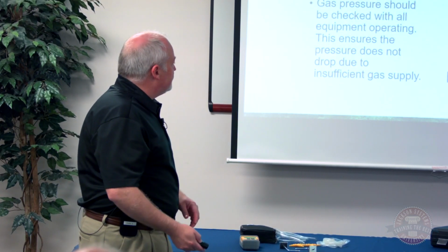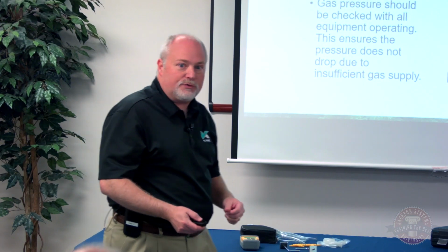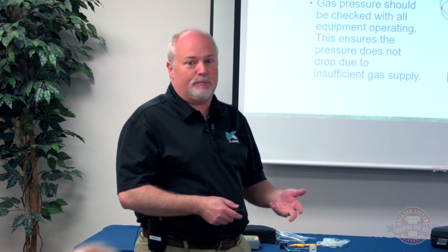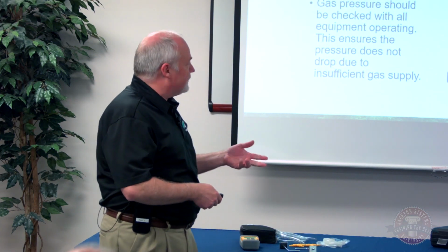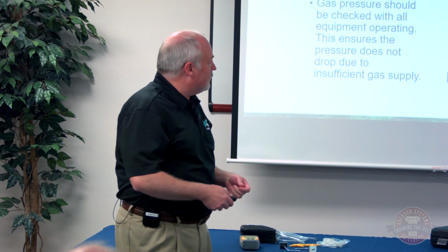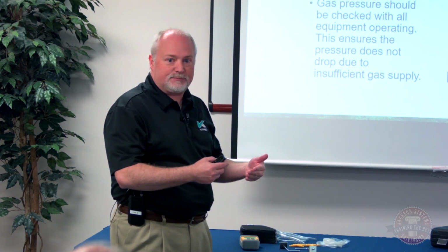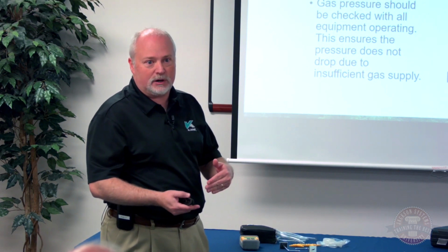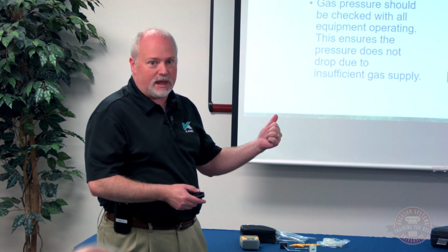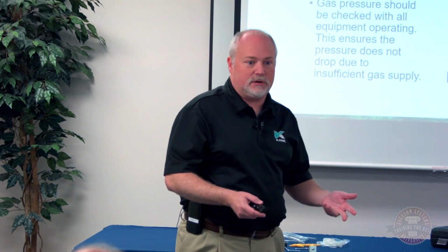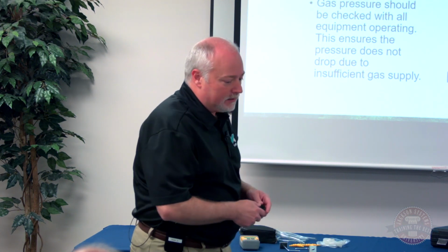One thing to remember too, a lot of gas valves have both a pressure tap for the inlet and for the outlet or manifold pressure. So you can check, this particular gas valve is a 2-stage unit. So if you need to adjust your gas pressure for the low fire versus the high fire, that's where you'd want to check that outlet or manifold pressure, so we know what that's operating at on your high and low fire rating.